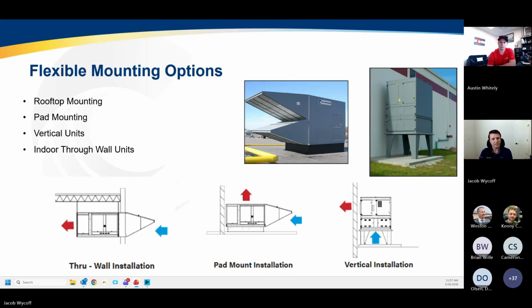The mounting for these units is also extremely flexible. So rooftop units are going to be very common for your new construction type spaces where they've already made accommodations to structurally support the unit. Pad mounted units are a great option as well for your retrofit applications where you want to mount the unit just outside on a pad. This is great because it's extremely serviceable from ground level. But if the footprint outside is a concern, we also offer vertical units, a little bit more difficult to service, but minimizes the pad you have to pour. It minimizes the footprint it takes up outside.